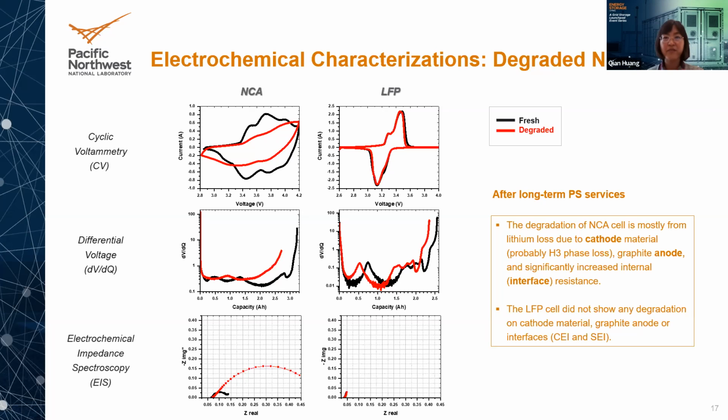Yeah, I think that's a very good question for the future of lithium batteries, especially for grid application. Right now, lithium-ion batteries still dominate grid applications based on the data, like 78% of battery systems. But for long duration, we are facing a lot of challenges. The most used right now is 4 hours or below, since the definition of long duration needs a discharge of 10 hours or more at rated power. So this is pretty challenging.